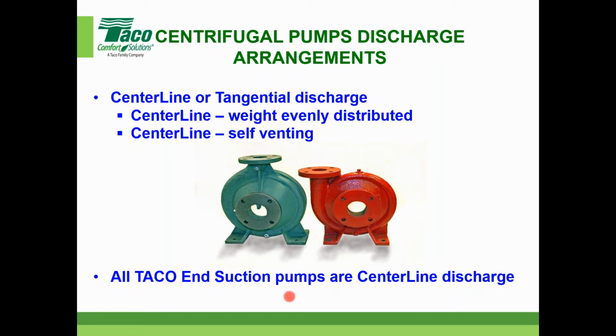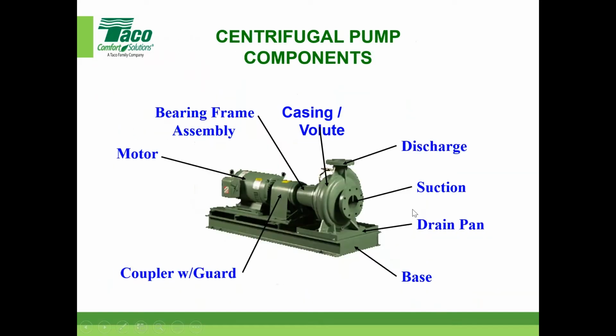All of our end suction pumps are centerline discharge. I'm sure these other manufacturers, in the old days before the DOE got involved, probably designed with tangential discharge because it gave a couple points higher efficiency—fewer internal losses in the pump. Our water had to get around the corner and out, theirs just had to go straight out. So anyways, just so you know: centerline versus tangential, a fundamental distinction there.